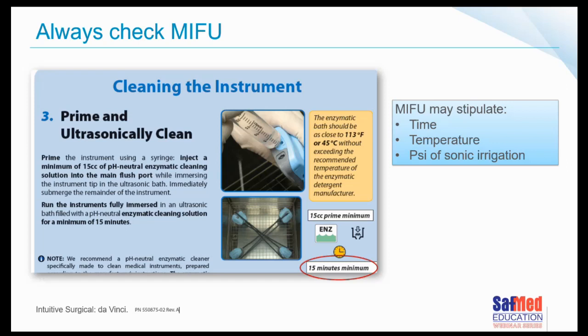In this case, it said the instruments need to go into the ultrasonic cleaner for a minimum of 15 minutes. They were also clear on temperature, recommending 45 degrees without exceeding the recommended temperature of the enzymatic detergent. It might also specify the PSI of the sonic irrigation or the kilohertz. So it's important to understand exactly what you're meant to do for that particular device before you put it in the ultrasonic cleaner.